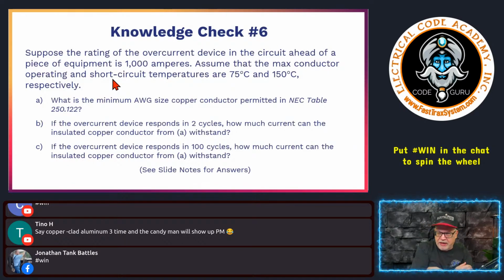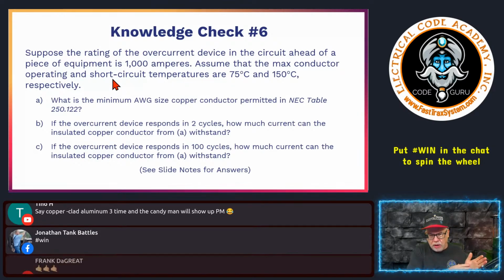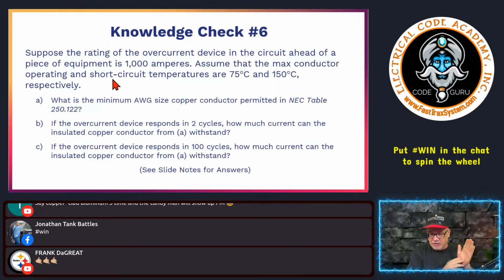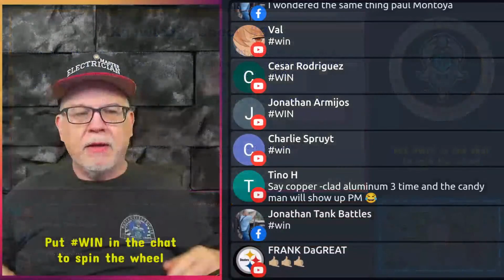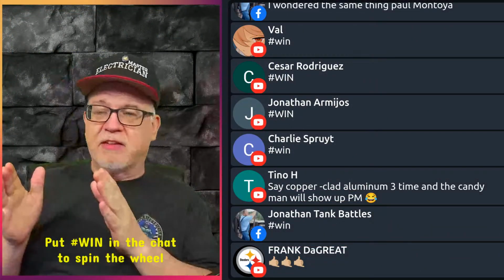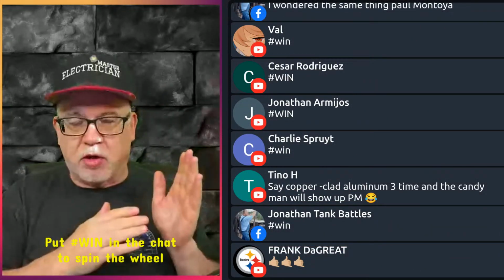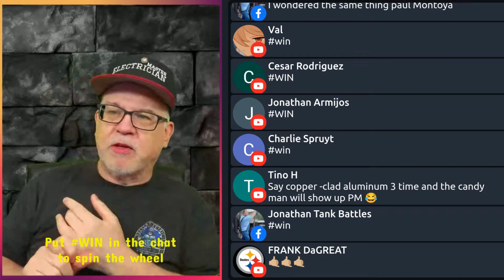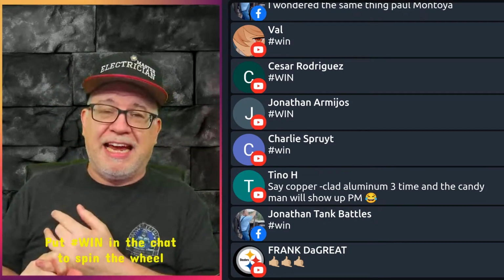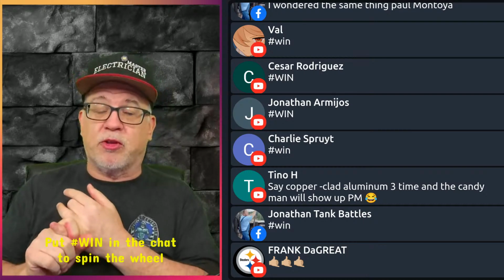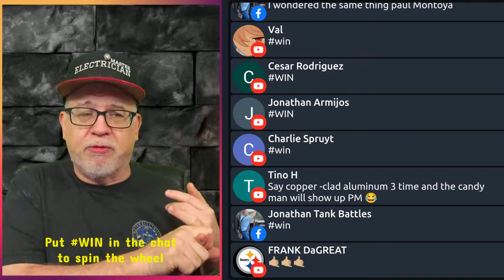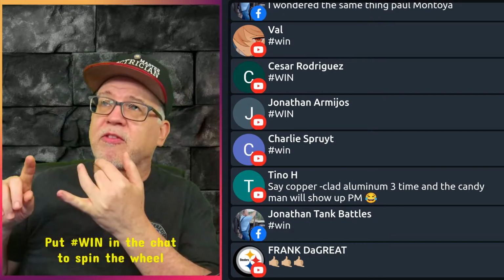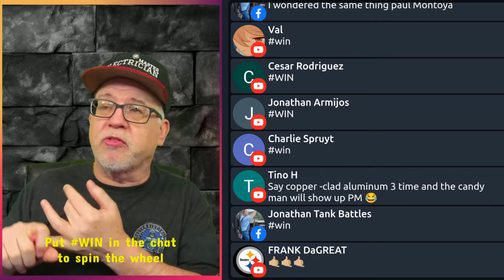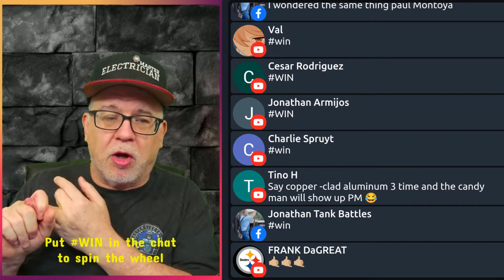Okay, now, let's check ourselves real quick here. And oh, and by the way, 250.122 again is based on the size of the overcurrent protective device. Okay, so I remember I told you there's 3 tables when it comes to your exam prep that you want to commit to memory. 250.66 deals with the size of the grounding electrode conductor based on the size of the overcurrent protected device. Okay. You've got 250.102, which is if you get a question that's asking you about sizing the minimum size for the grounded conductor, which you're going to get there by 250.24 anyway. It's going to send you there. It's supply side bonding jumpers. You'll go there for the rules. The system bonding jumper, you'll go there for the rules.